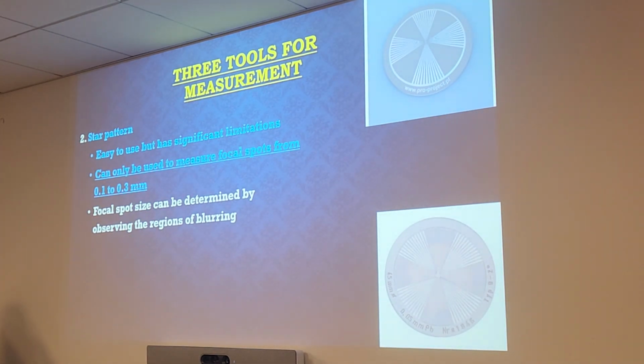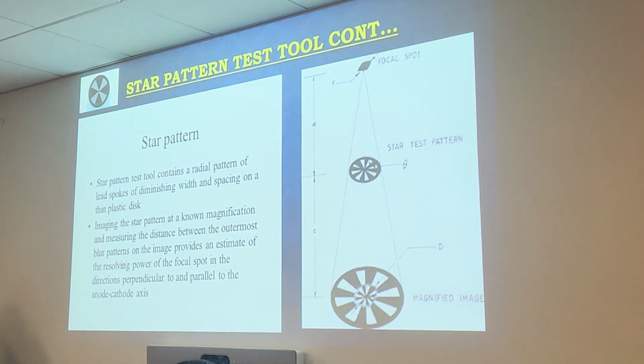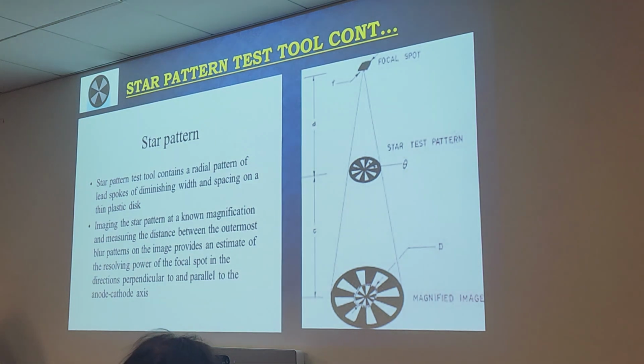Alright, the next one is the star pattern. So this one is a little bit easier to use, but it has limitations. You can only measure focal spot sizes from 0.1 to 0.3 millimeters. And basically this test is used to measure the blurring region around the focal spot size. So this is kind of an example of what the star test pattern looks like.